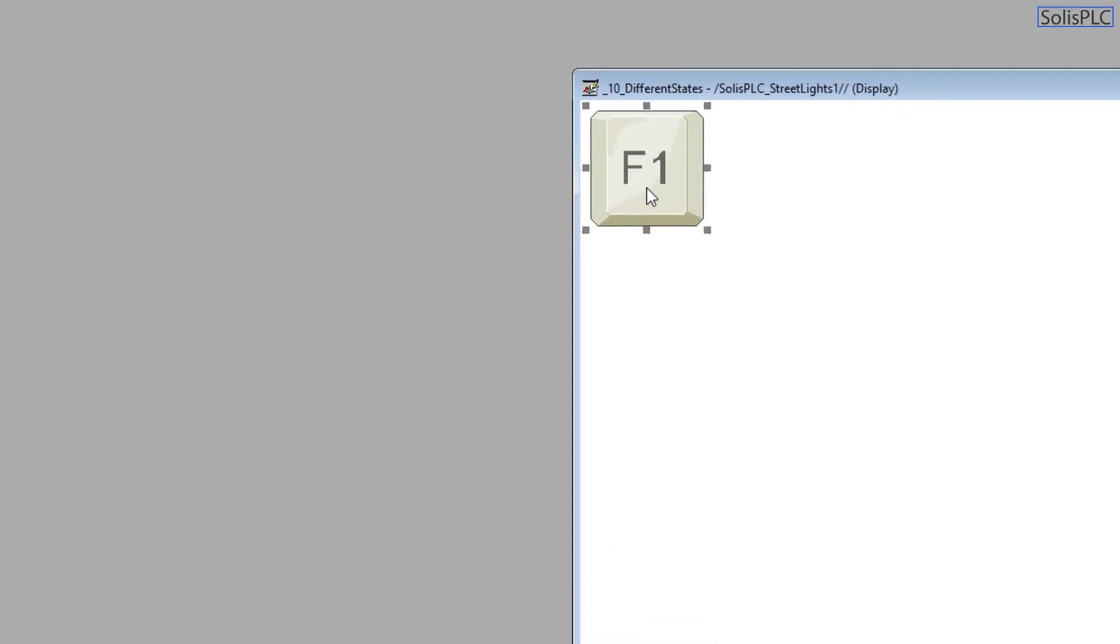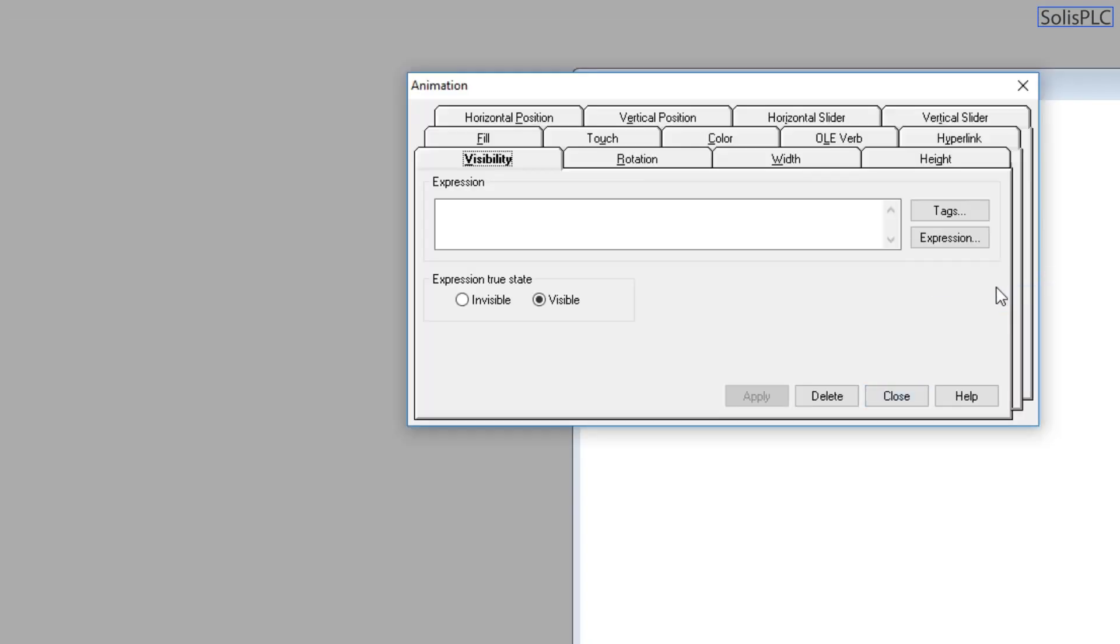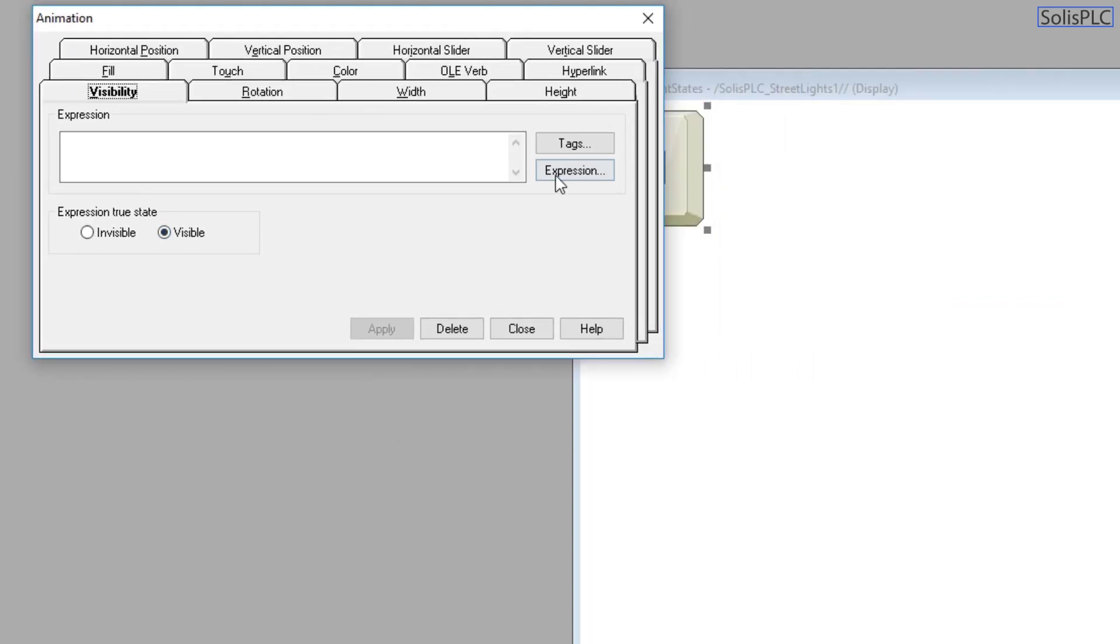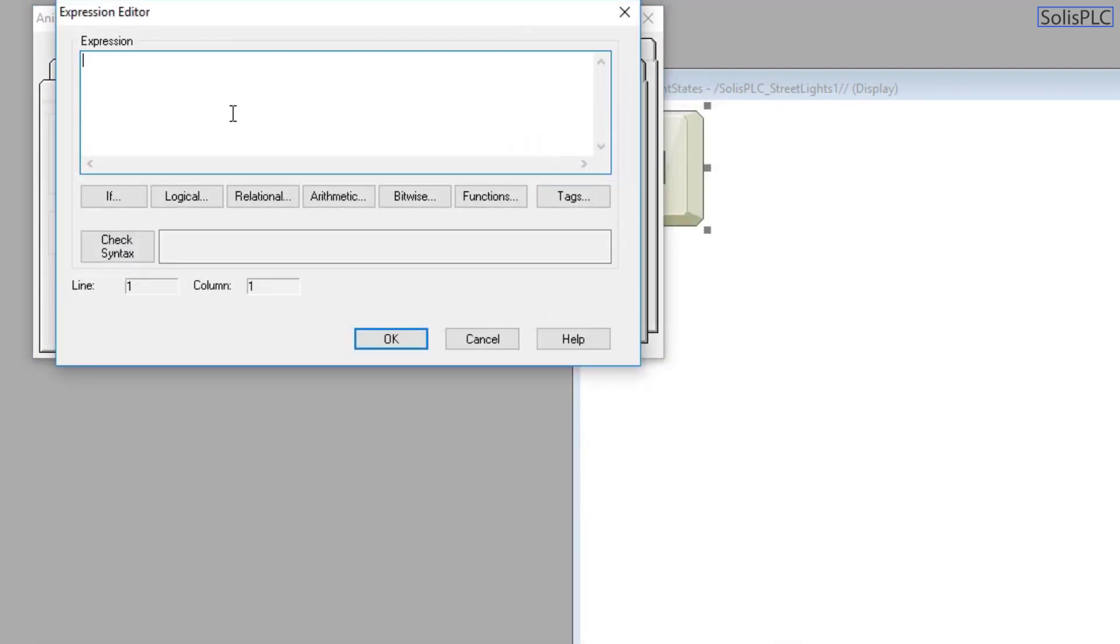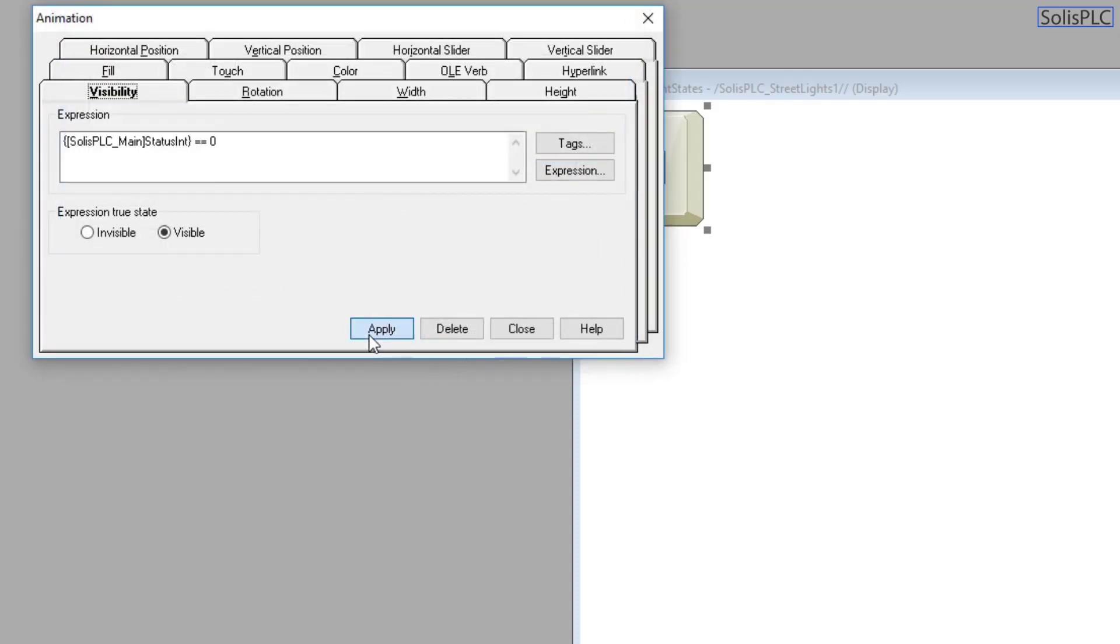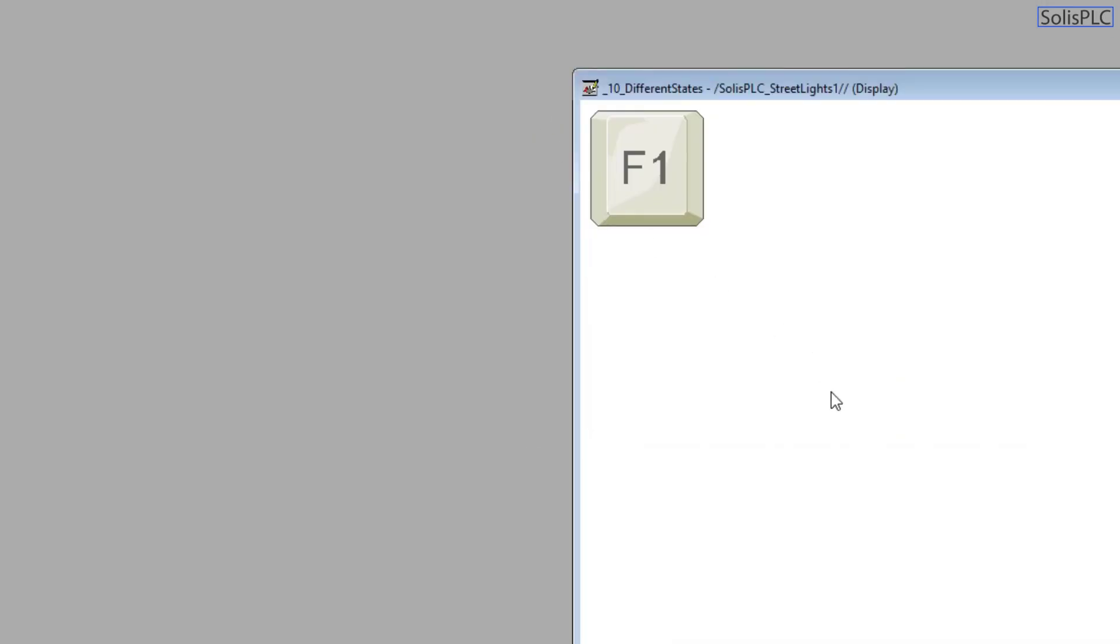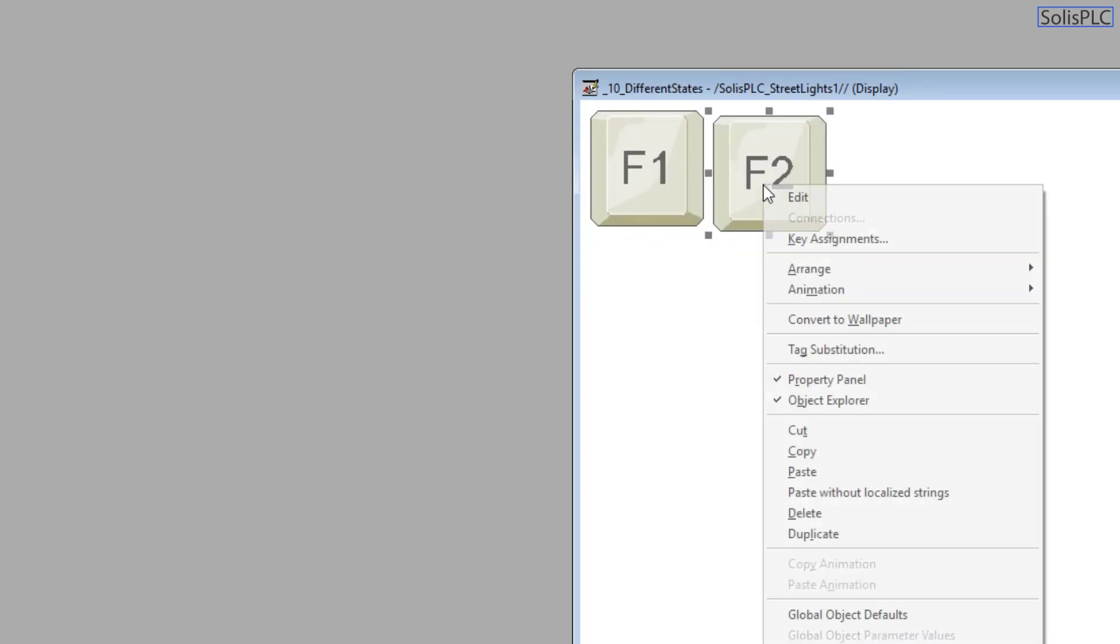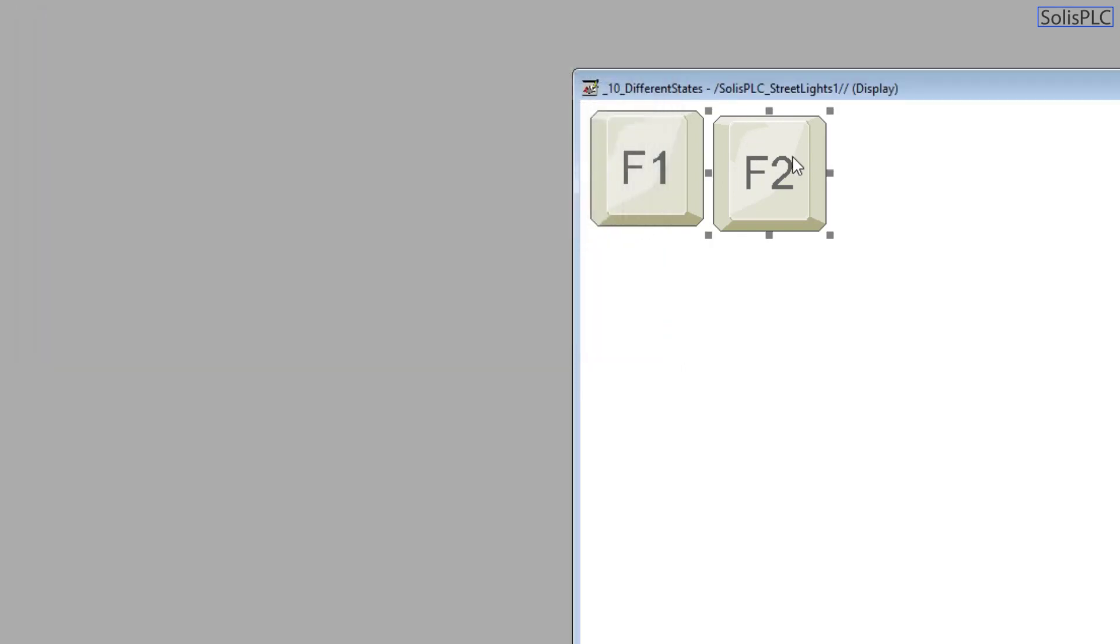Let's look at the property we're going to need to set on this, so animation, I'm going to go into visibility this time. It's not going to be the color, but it's going to be visible when. It's going to be an expression, so it's going to be tag, and then we're going to find the same tag, but instead of just writing the tag, we're going to say that it's equals to zero. When the tag is equal to zero, this is going to become visible. Now we go back to the Symbol Factory, we take the second image that we want to paste, and we paste it on top of it. Let's just put them next to each other for better visibility.